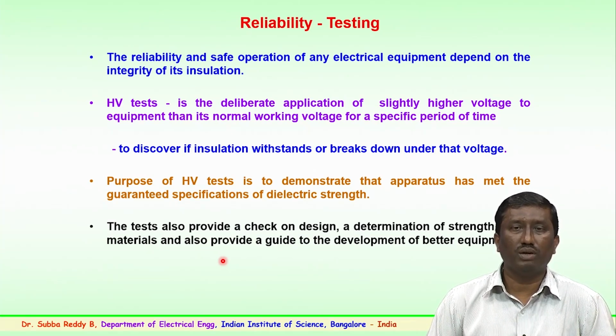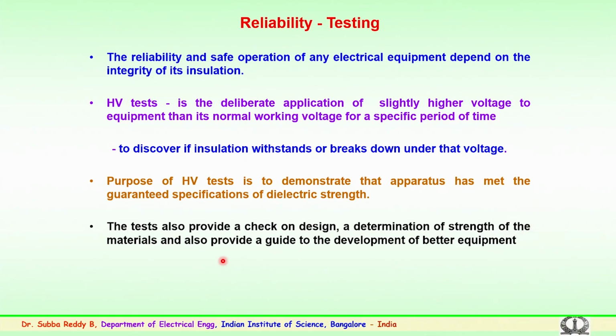So, the purpose of the high voltage test is mainly to demonstrate that any apparatus meets the guaranteed specification for the insulation or the dielectric strength for which it is designed. These high voltage tests also provide a check or verification on the design which is to be put up in the field, a determination of the strength of the materials being used as insulating media, and also provide a guide to the development of better equipment, in case the insulation which has been used has to be upgraded or further improvement could be carried out. So, this helps the reliability and helps to achieve better insulation for the equipment to be used in the transmission or the distribution systems.